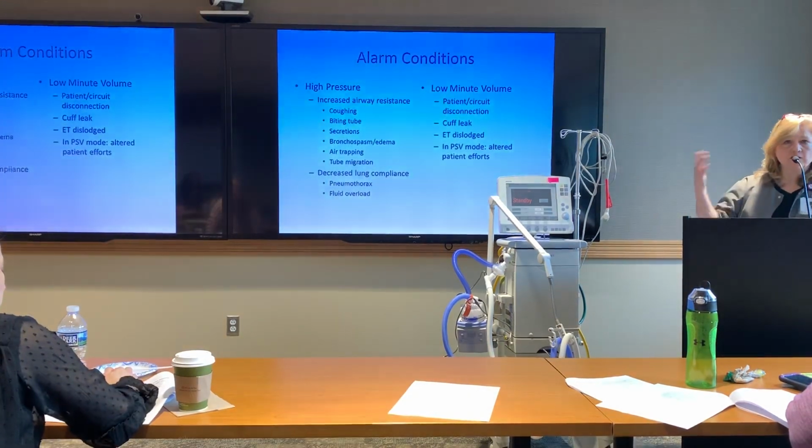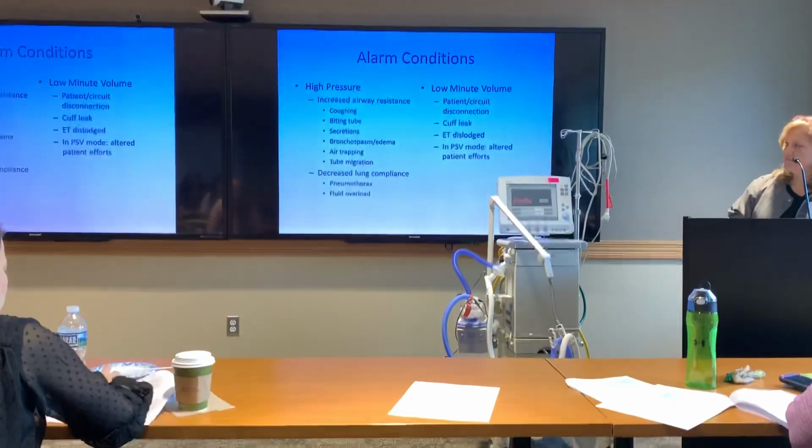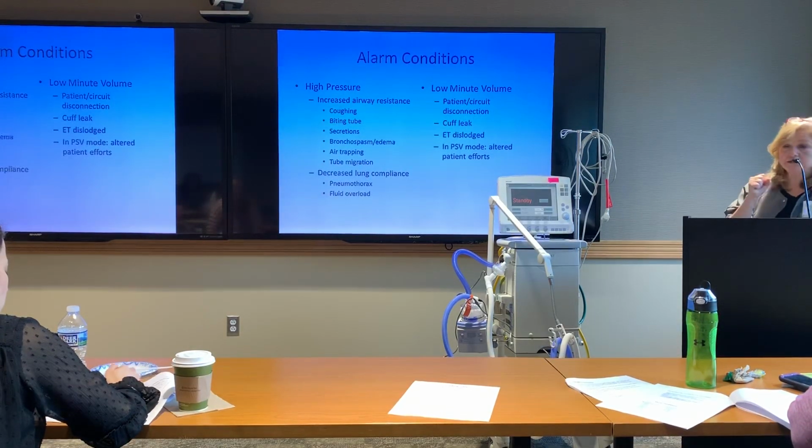Okay, he also asked me to talk about alarms. So I'll talk about the ones that generally occur on this ventilator. The high pressure alarm goes off, okay? Causes.